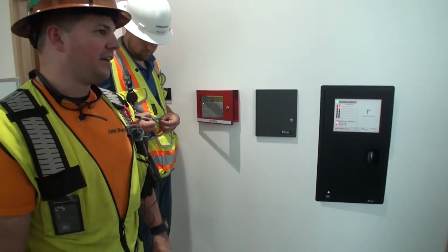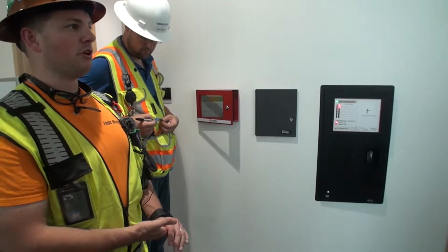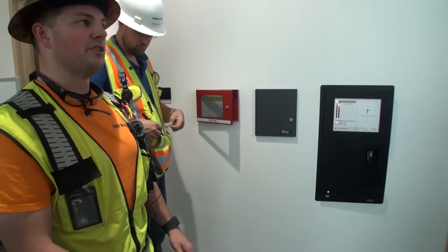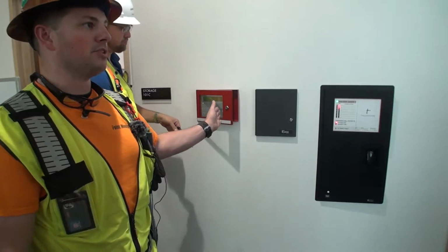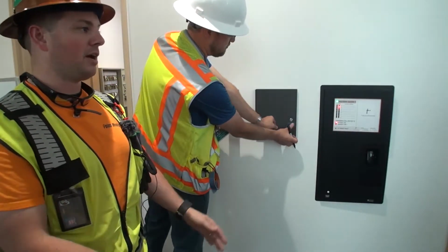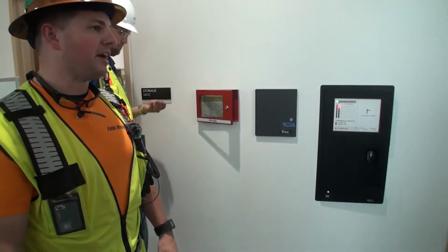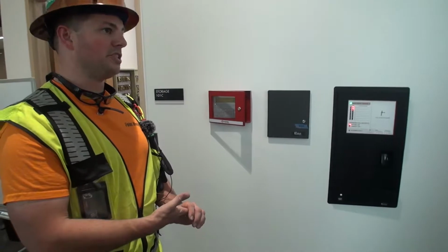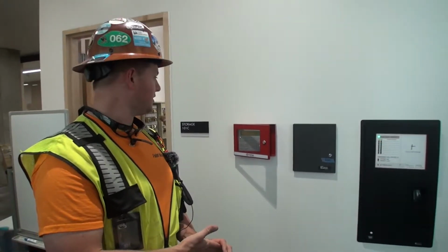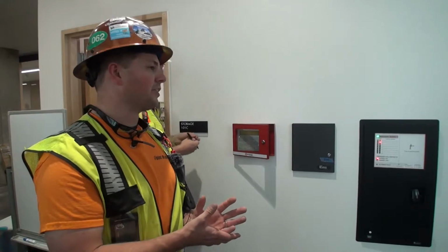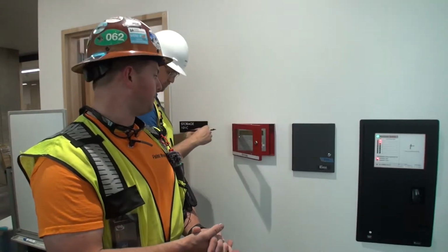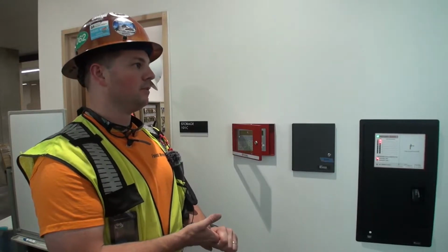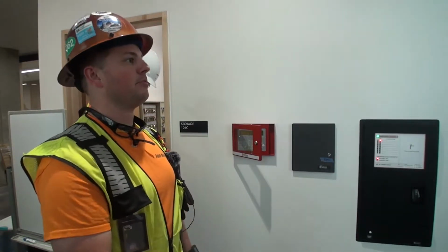If there's any problem with the system, you'll have a trouble, gets reported out to Central Station, and then Portland Public Schools will get a phone call or email or however you have that set up. But it will display where the trouble is located here, and an authorized person will need to come and fix that trouble. On a supervisory, which is just a piece of information that somebody needs to know about, will report here and do the same with a different format, telling you your sprinkler doesn't have water available, or your Ansul hood is activated, or whatever other supervisory inputs we might have here.